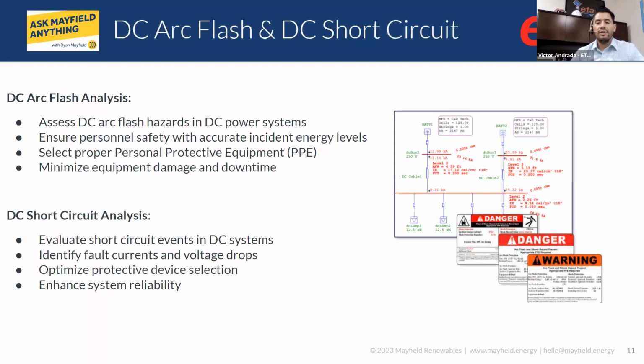And then Clayton, for DC, I know that we do a few methods, especially for PV installations. Yeah, so Victor, I just want to go through how you can use ETAP to mitigate those risks and really ensure safety and compliance throughout the system, your DC network specifically. So actually, DC arc flash and DC short circuit are two separate modules within ETAP. As Ryan discussed earlier, ETAP is modular. You can pick up different modules based on your needs. And these are two separate modules, but in fact are integrated together.